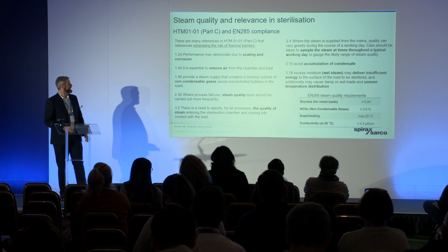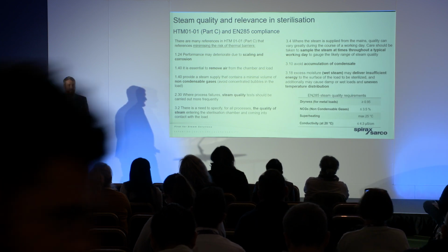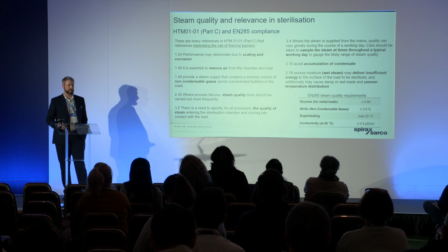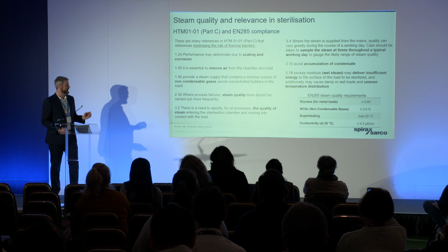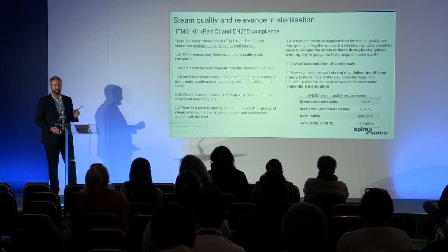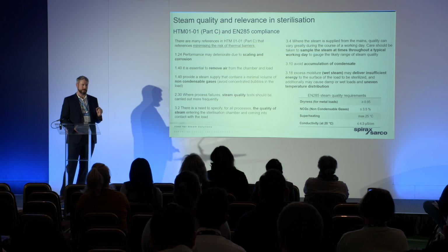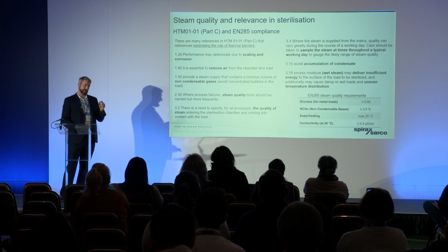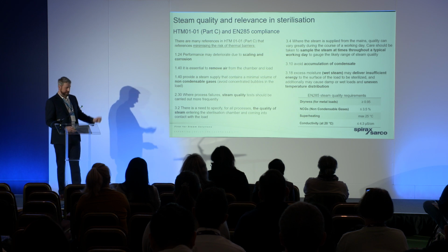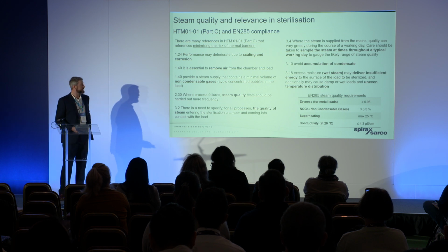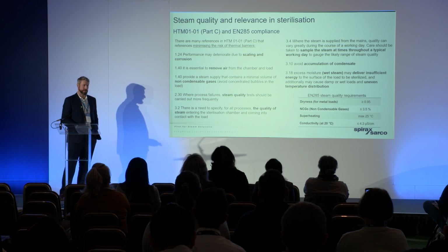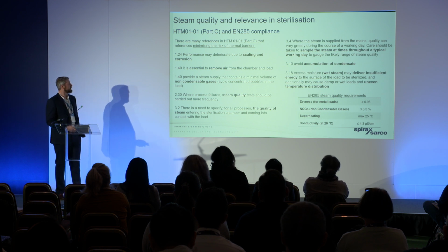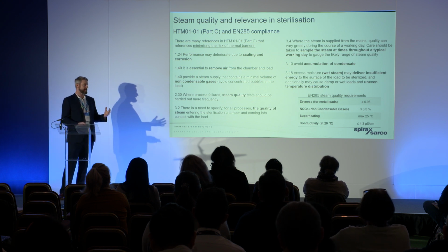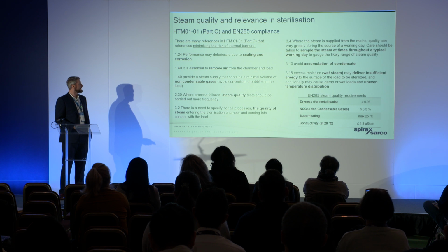So, we know we've got HTM 0101 and we have EN 285 compliance, all governing what we do with steam in sterilisation. So what I've done here, it's very wordy, this slide, and apologies for that, but what I've done is I looked through this document and I've picked out the really poignant references that point to heat transfer and that really important heat that's transferred to sterilize the equipment. And there's things that come up like with the feed water to avoid scaling and corrosion, because that can create a barrier to heat transfer. Making sure we remove air from the chamber, because air again can be that barrier for heat and sterilization.